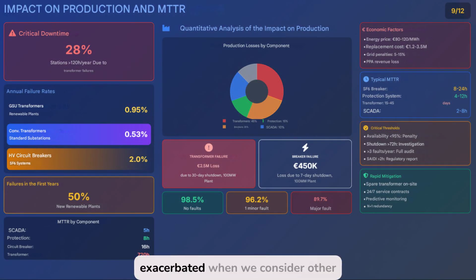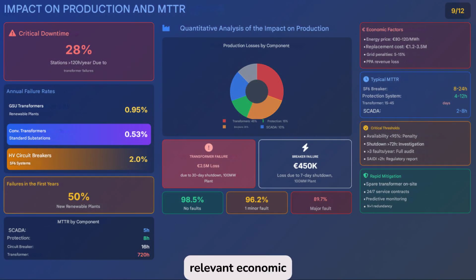This problem is exacerbated when we consider other relevant economic factors. The price of energy ranges between 80 and 120 euros per MWh. The cost of replacing a transformer is between 1.2 and 3.5 million euros, and penalties for unavailability can range from 5% to 15%, not to mention the loss of revenue associated with balance sheet deviations or breaches of PPA contracts. Furthermore, insurers and financiers are beginning to require more rigorous maintenance and reliability metrics as a condition for extending coverage or approving investments, which adds additional pressure on operators.